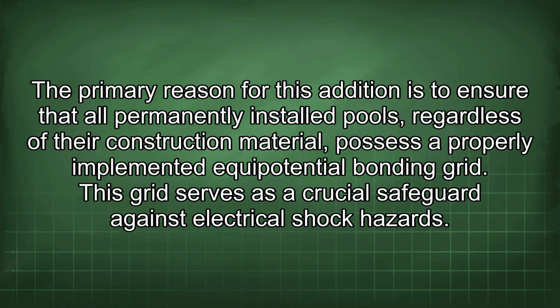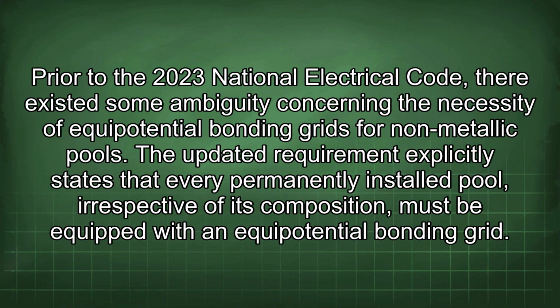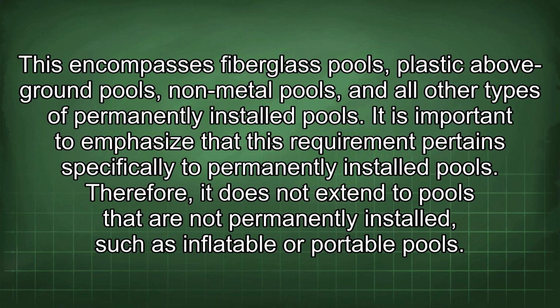The primary reason for this addition is to ensure that all permanently installed pools, regardless of their construction material, possess a properly implemented equipotential bonding grid. This grid serves as a crucial safeguard against electrical shock hazards. Prior to the 2023 National Electrical Code, there existed some ambiguity concerning the necessity of equipotential bonding grids for non-metallic pools. The updated requirement explicitly states that every permanently installed pool, irrespective of its composition, must be equipped with an equipotential bonding grid. This encompasses fiberglass pools, plastic above-ground pools, non-metal pools, and all other types of permanently installed pools.